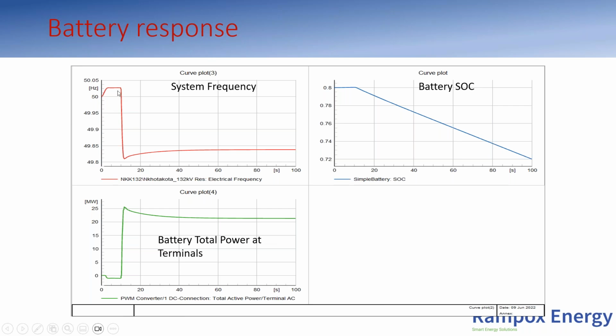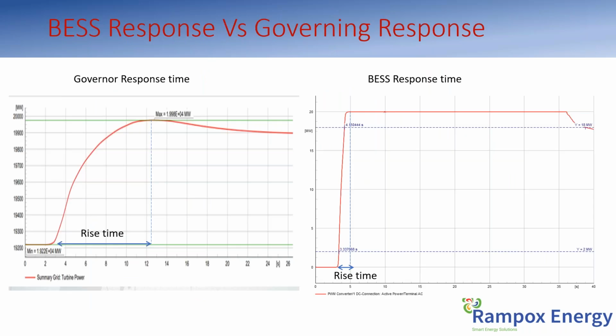I think that's what we need to understand, that batteries have this type of response. As you can see the frequency going down there, you can see the response the battery has—it's almost instantaneous. This is one of the simulations we're doing, coming mainly from Malawi. If you check the response of the battery versus the governor, on the left-hand side you see the governor rise time—because of those mechanical time constants, the rise time is very slow. Then look at the battery rise time—for those who remember control systems, it's very high, and that's exactly what you want.